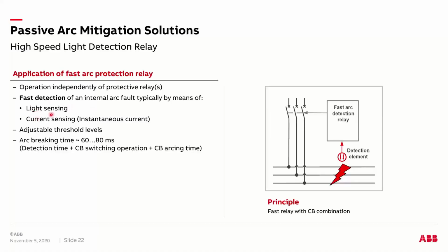So in conjunction with this light sensing, we also add another function, which is an AND function, right? So when we put in the current sensing, instantaneous current sensing, we do not risk any kind of nuisance tripping, right? So if you use a REA 101, which is an arc flash relay, with these two parameters, we are definitely going to be 100% sure that you have an arc flash incident that is developing within your equipment, and within less than 2 milliseconds, the REA relay or an arc flash relay can send a trip signal to your main incoming breaker.